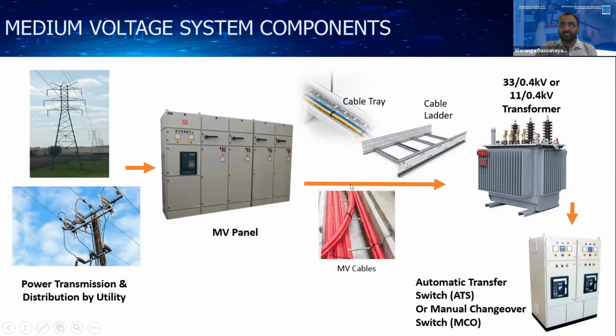The cables may be in a cable tray or a cable ladder. So if you are going to visit the site, please inspect how these cables are installed, whether in a cable tray, cable ladder, or a trench, because the installation method is very important. If you install a cable underground in a cable trench, the current carrying capacity of the cable may be reduced compared to installing it in a cable tray or cable ladder.